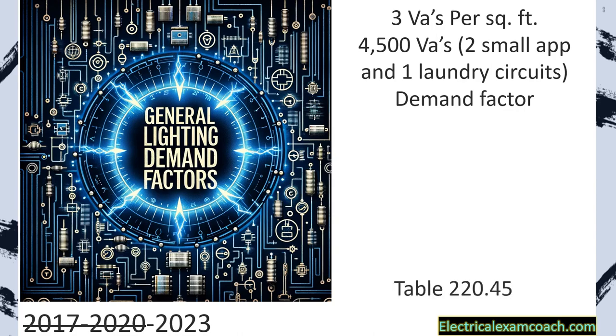We're going to head to table 220.45 for this. When we get there, the first thing we're going to do is read our table and make sure that we're in the right table. It says lighting load demand factors — I feel good about it. Now looking at the table, we read all of our tables from top to bottom, left to right, using our black bold headings to navigate the table.